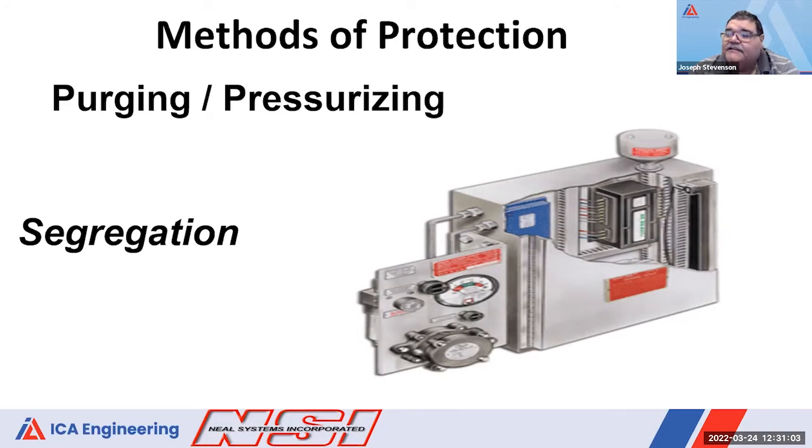So Dave, you have a purge panel out on the loading area. We have two of them. Yeah, two of them in the area: the blending tanks, that project we do with you, and then the drum filler house. Right. And that's the thing. When that facility was designed, intrinsic safety was apparently not considered, or wasn't known at the time, so you end up with a purge panel. Part of the issue too is that you have a touch screen out there, and that had to be in the purge box, behind glass, so it could be within that pressurized envelope. Right, that's right.